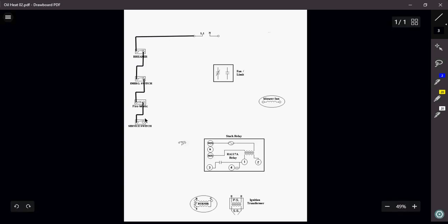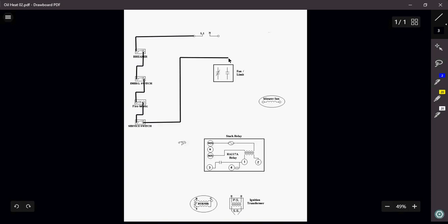Now we're going to come and we want to wire in the fan limit switch. So now the fan limit switch really is ultimately just two switches that are wired in parallel with each other. Okay, so we're going to have power coming in over here and we're going to have power here. Okay, normally closed, normally open.